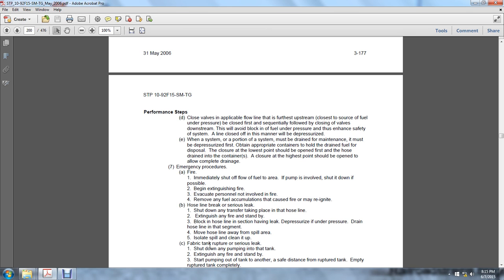When a portion of the system must be drained for maintenance, it must be depressurized first. Obtain appropriate containers to hold the drained fuel for disposal. The closure at the lowest point should be opened first, and then the hose drained into the containers. The closure at the highest point should be opened for complete drainage.